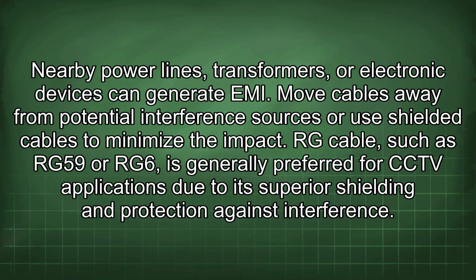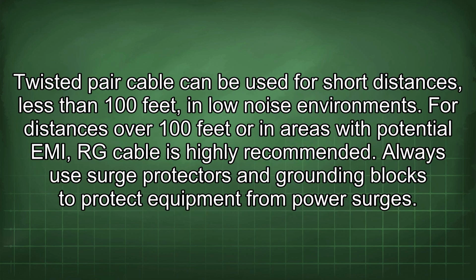RG cable, such as RG59 or RG6, is generally preferred for CCTV applications due to its superior shielding and protection against interference. Twisted pair cable can be used for short distances, less than 100 feet, in low-noise environments. For distances over 100 feet or in areas with potential EMI, RG cable is highly recommended.